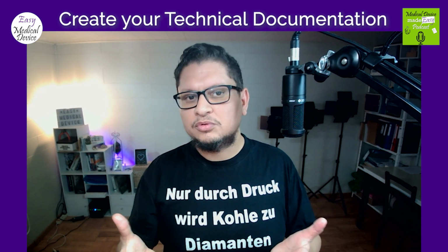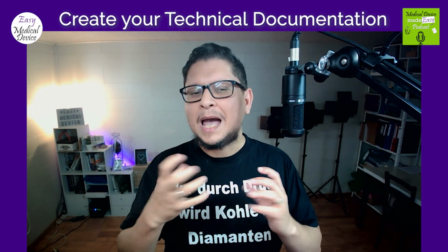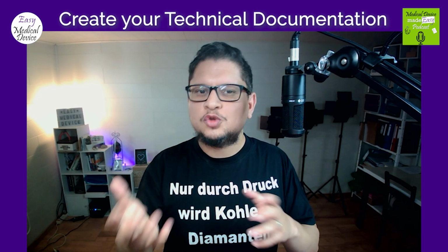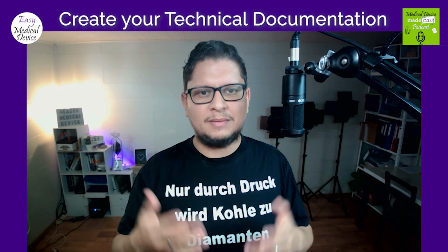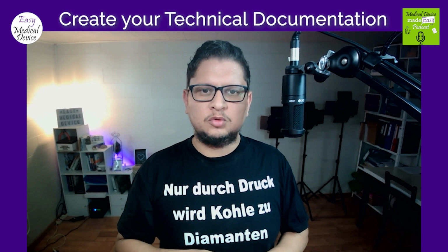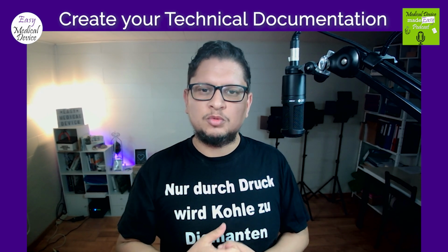Also similar products on the market, not equivalent, similar. So here is also this distinction between similar and equivalent. I always write in this section that these products are similar but not equivalent, just to make it clear, because when you do the clinical evaluation report and you talk about equivalency, you also have to make a distinction between similar and equivalent. You also have information about where this product is sold, outside of Europe maybe, or maybe even in Europe. So you have this device description to provide.